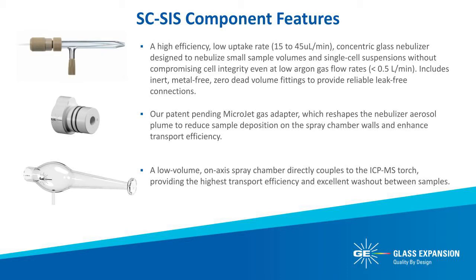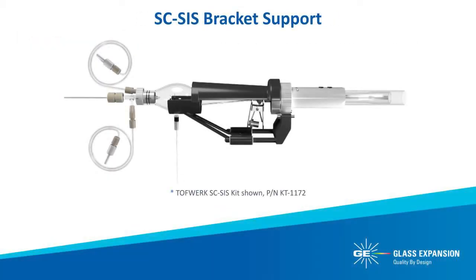Last but not least is our low volume on-axis spray chamber, which directly couples to the ICP torch, providing the highest transport efficiency and excellent washout between samples. In addition to high performance, it is also important to provide a simple and reliable means of installation, ensuring that the single cell sample introduction system is properly aligned and supported on each instrument.